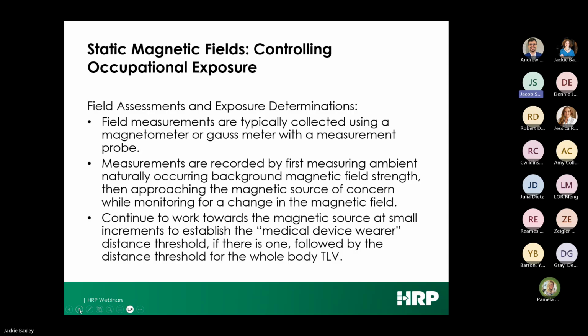We usually start by backing up as far as you can to establish your baseline numbers, then keep working toward the magnetic source at small increments to figure out where the fields start and stop, with the goal of establishing that medical device wearer limit. If you've used real-time meters with gas detection or similar, you'll notice a lot of variation based on how you're holding and orienting the meter relative to the part, so taking many measurements and varying orientation is important to capture the actual field layout.